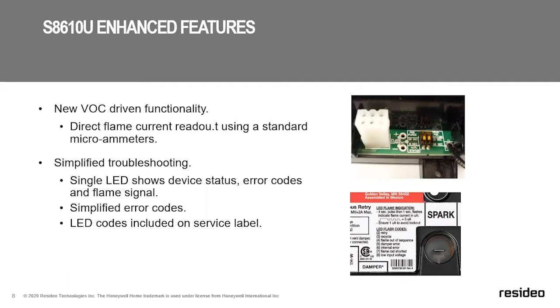You have points there where you can put your microammeter and see what your flame readout is. Another nice thing, like I said a little bit earlier, is there's an LED on there that shows you not only the device status, what mode it's in, or what point it's in in the ignition process. It also gives you the most common codes, and it tells you what the codes are and what you need to do according to the code to resolve the issue.